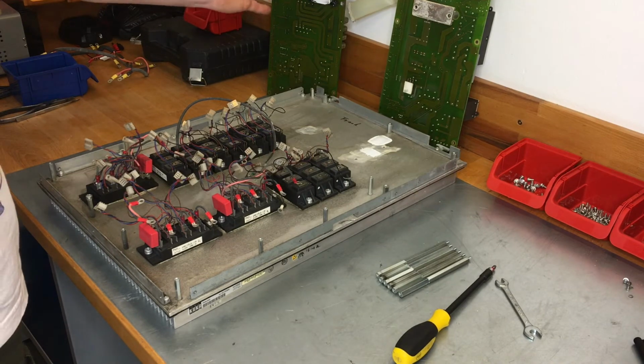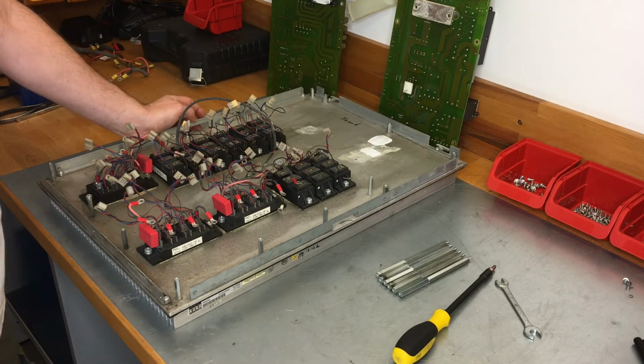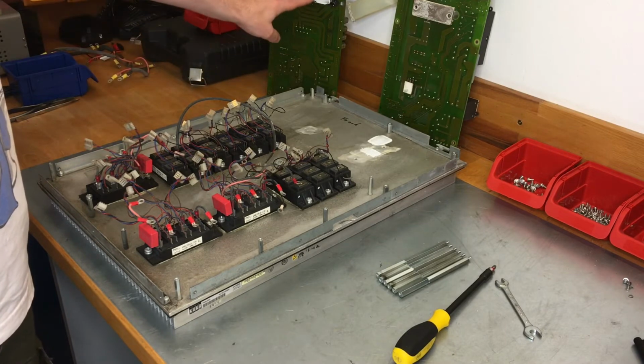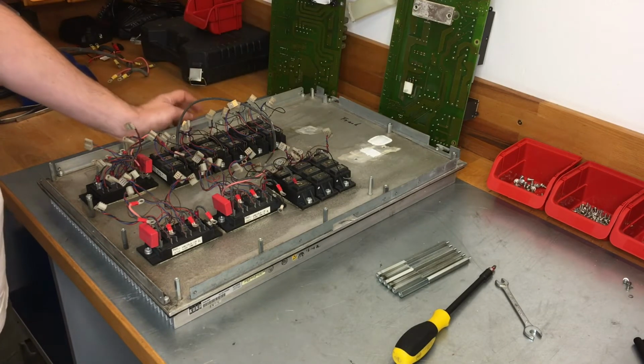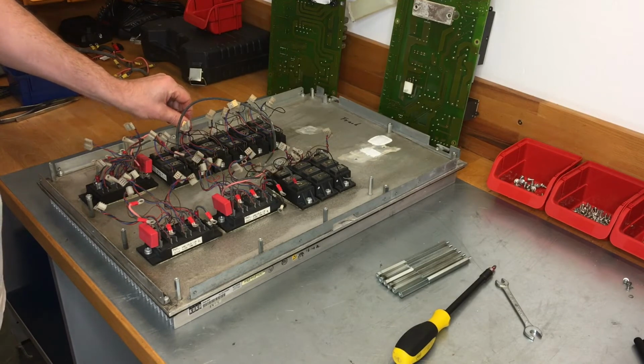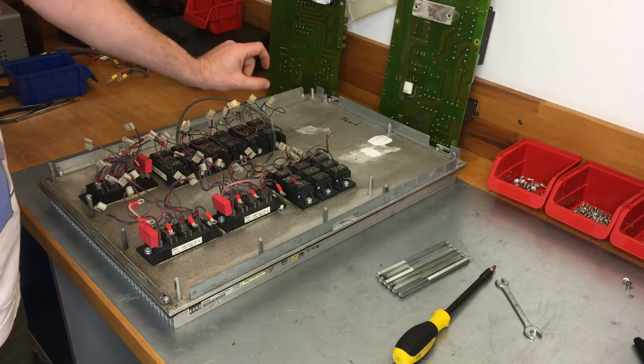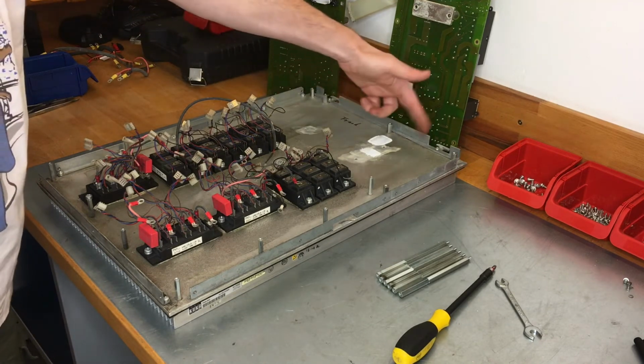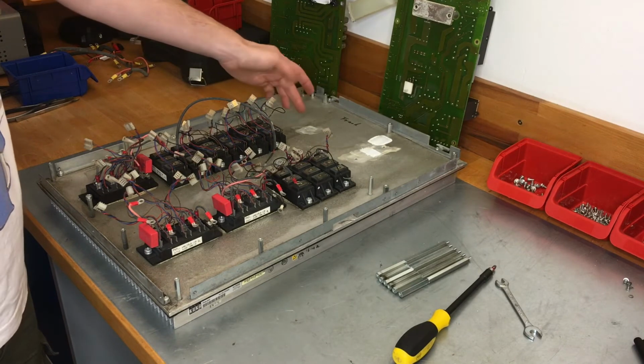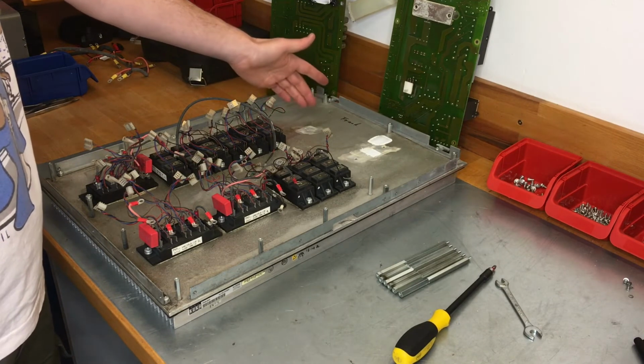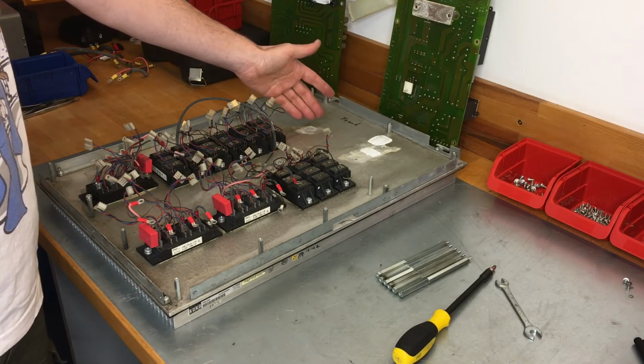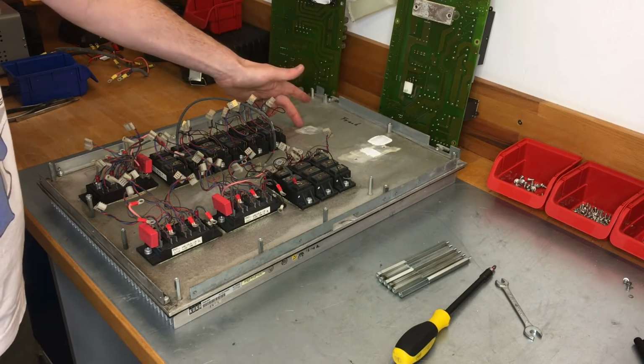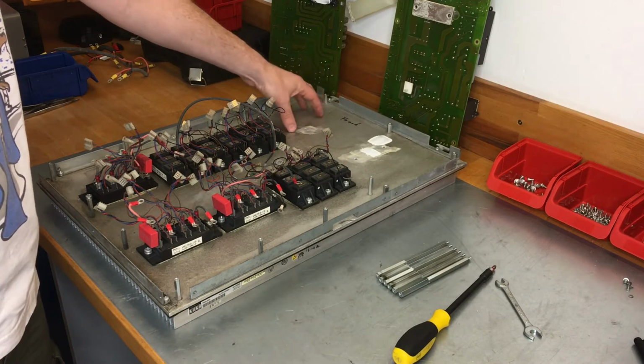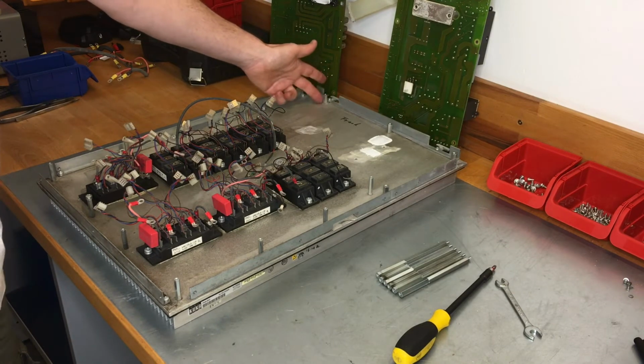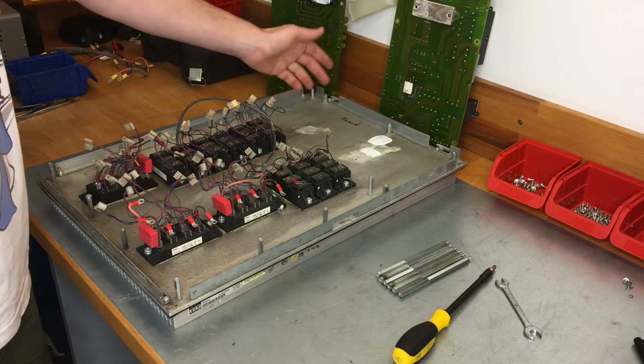As mentioned before, you can see now why the high voltage power supply is only partly interchangeable between the two models. Simply the position of the components that need to be cooled is slightly different, and the height is also different, which means that the spacer bolts would also have to be replaced, but it's not impossible. On the newer model, the screw positions are provided for both, so you can fit both boards in the newer enclosure if you change the spacers. In the older model, however, there are no screws to fix these two components to the enclosure, but everything is within the realm of possibility.